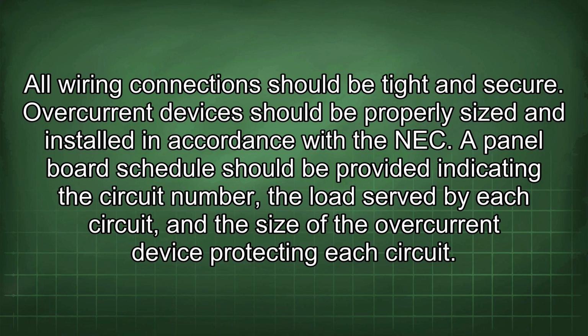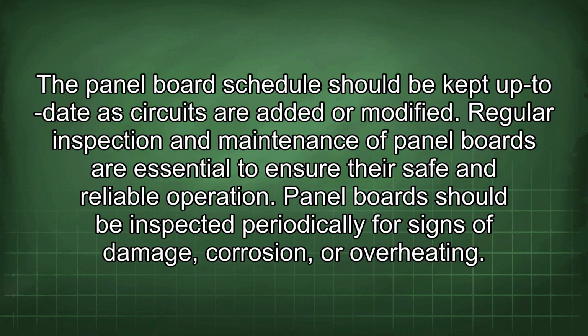A panel board schedule should be provided indicating the circuit number, the load served by each circuit, and the size of the overcurrent device protecting each circuit. The panel board schedule should be kept up to date as circuits are added or modified. Regular inspection and maintenance of panel boards are essential to ensure their safe and reliable operation.